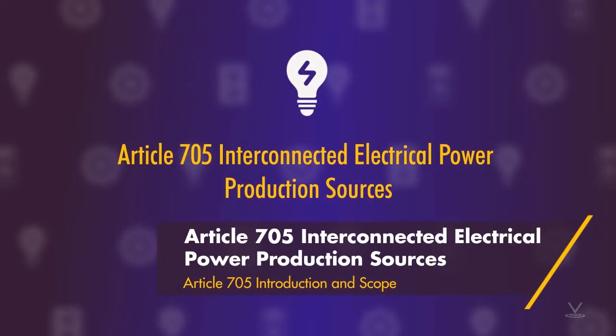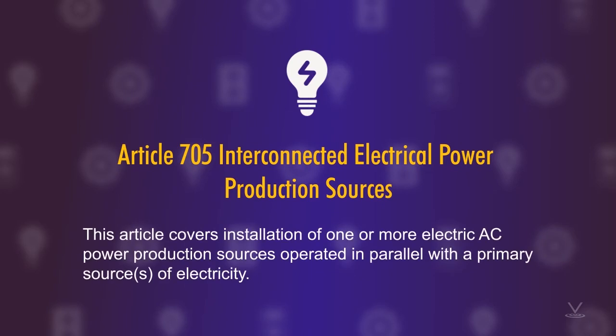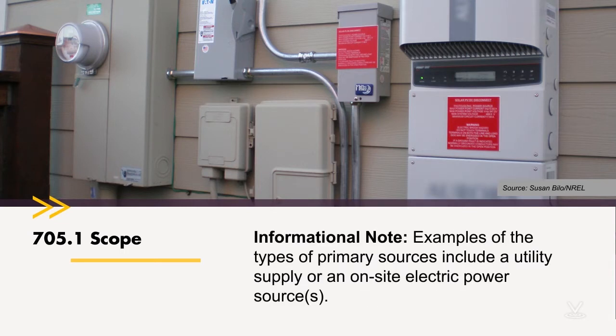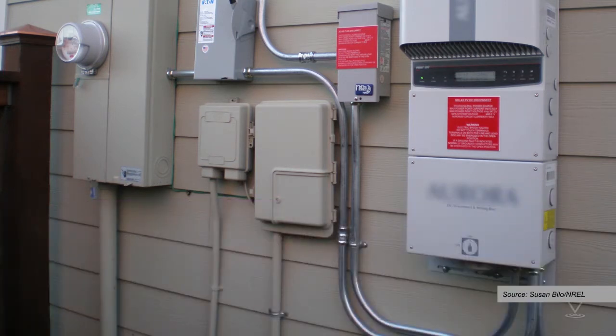This article covers installation of one or more electric AC power production sources operated in parallel with a primary source of electricity. What's a primary source of electricity? There's an informational note for that. Examples of types of primary sources include utility supply or an on-site electric power source — it could be a large diesel generator on an island, for instance, that we're interconnecting with as the primary source. But most often, in most of the systems in the United States, the primary source is going to be the utility.